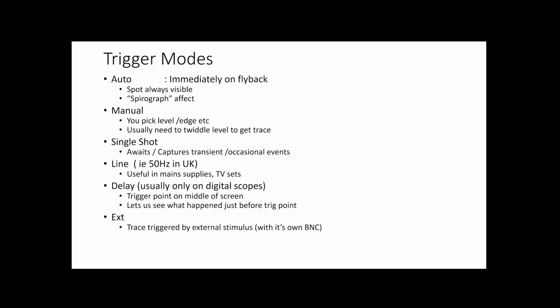You click it into manual mode, then you pick the level and whether you want it positive going or negative going. And generally what you'll have to do there is twiddle it to get the trace. A thing that you'll find happens is you put it into manual mode and you get nothing. And the reason you get nothing is that the level is set too high or too low for your waveform.